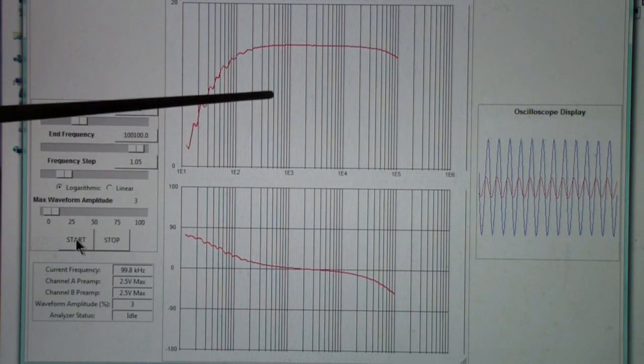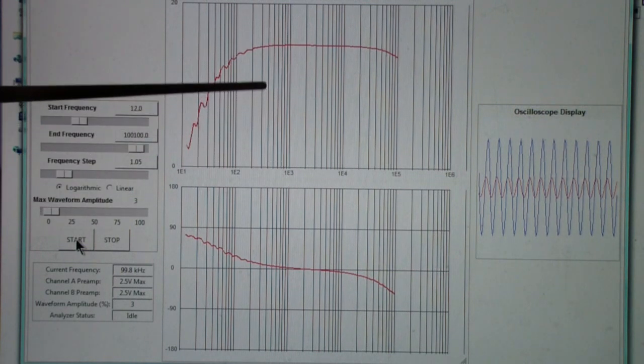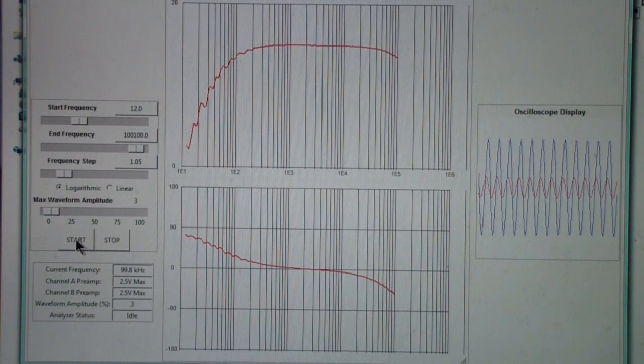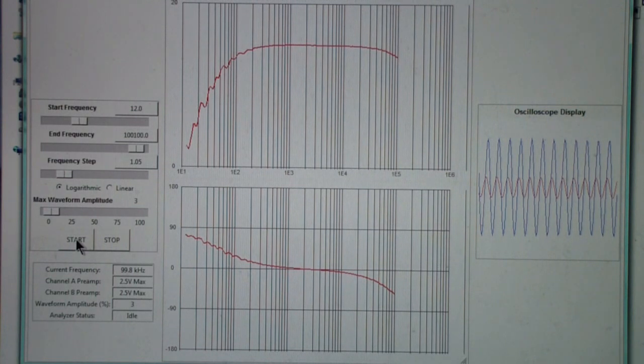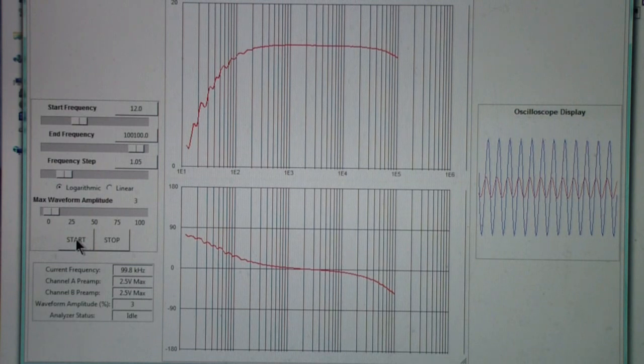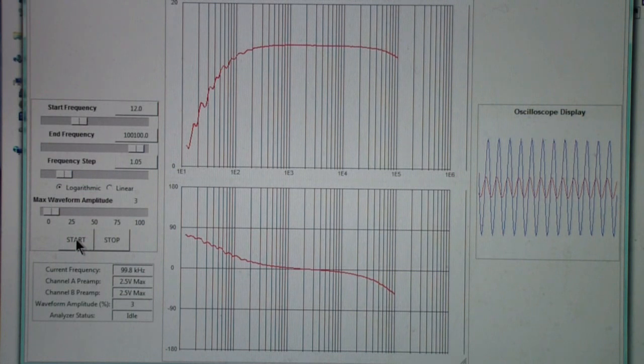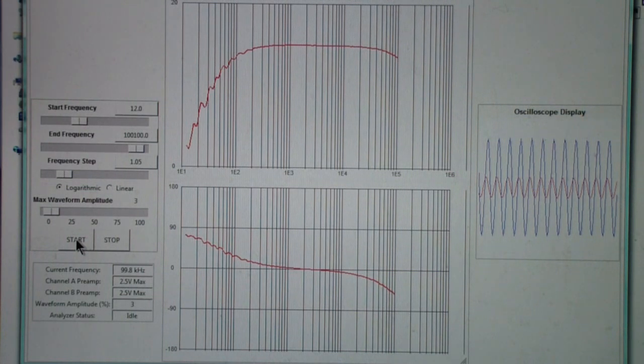Now, one of the limitations of the SIG 101 is it only goes to 200 kilohertz, but then I only paid a hundred dollars for it. So it's not intended to be a very high frequency instrument.